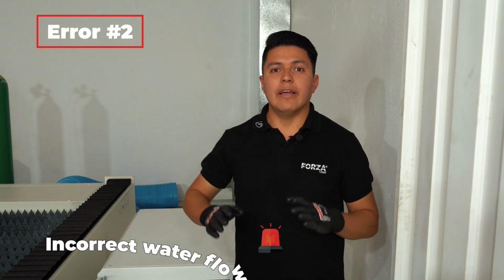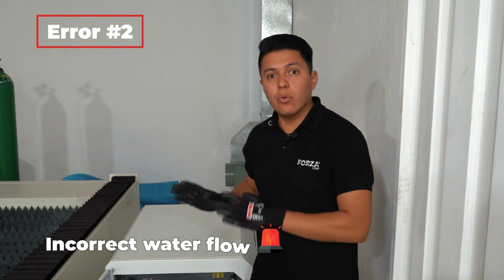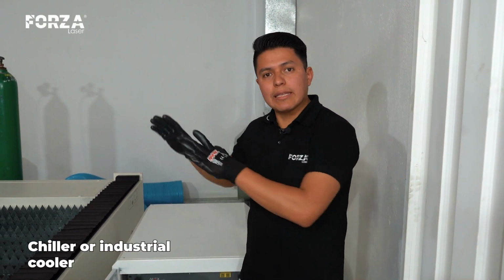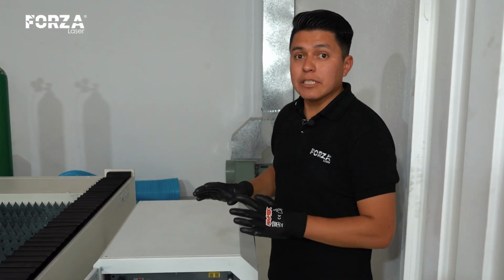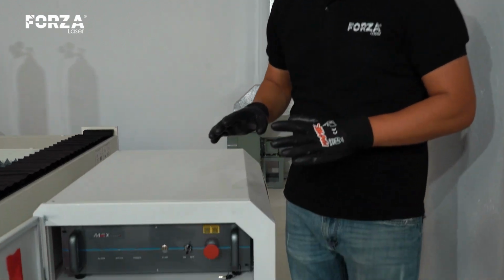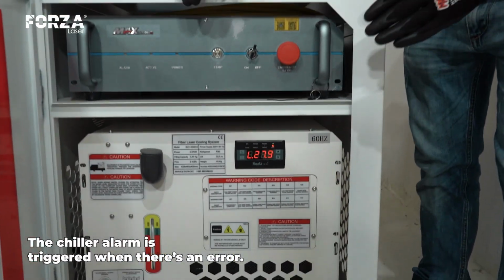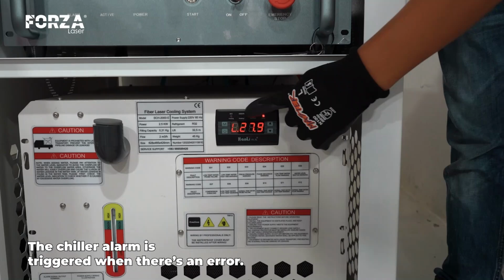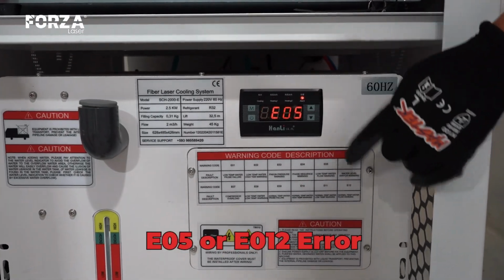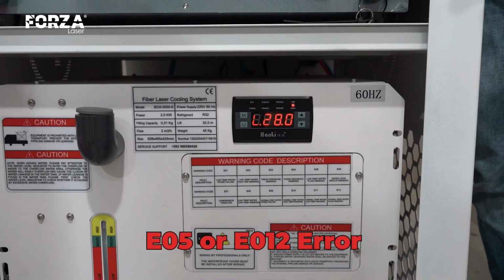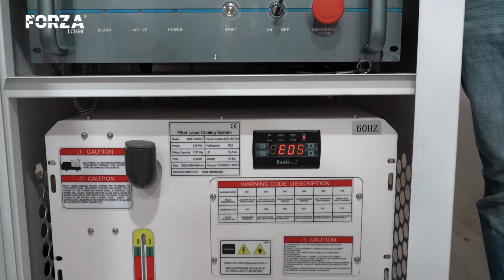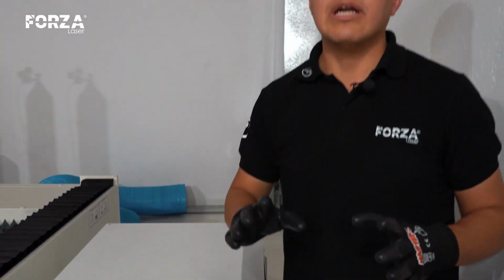Error number 2, incorrect water flow. Remember that the chiller cools the laser source part and the laser head part, and it sends water through the ducts. If any of these ducts is crushed, we'll see an alarm, either the E05 or the E12. The first error, the E05, refers to a lack of flow in the laser source. And the second error, the E12, refers to a lack of flow in the laser head.